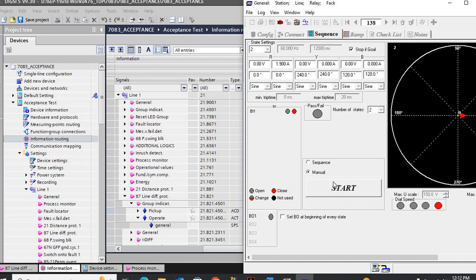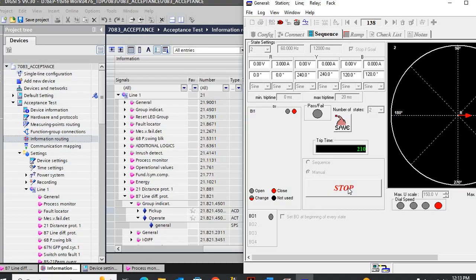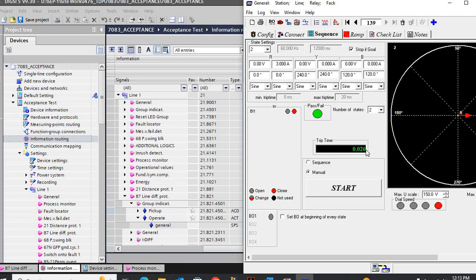The differential will trip after 3 seconds. If it is a heavy fault — actual fault — it will consider a differential trip and will trip instantaneously. So if less than the threshold value, the differential will not enable. If less than or nearby the switch-on-to-fault condition, it will consider that the line order is closed and this is not an actual fault, so it will trip after 3 seconds.